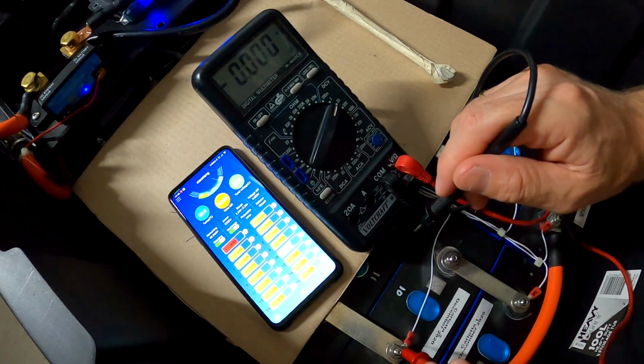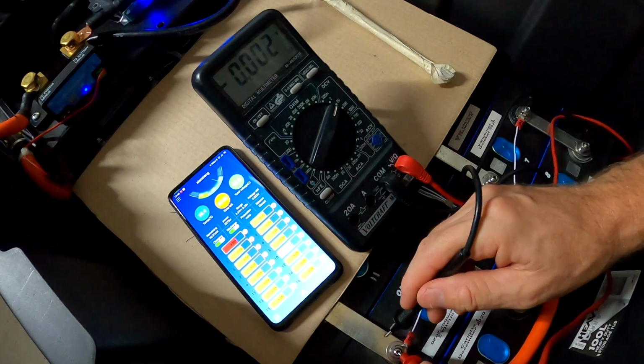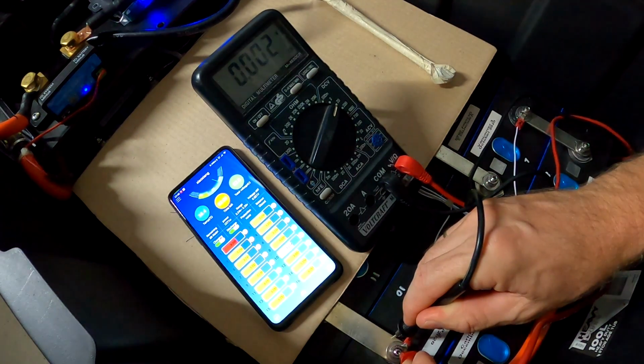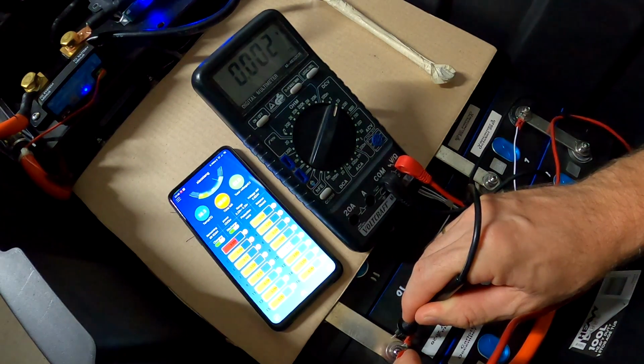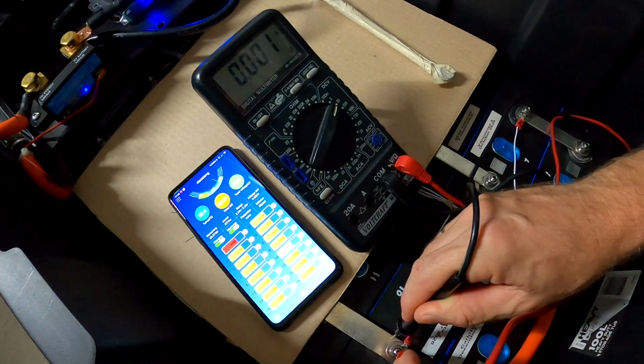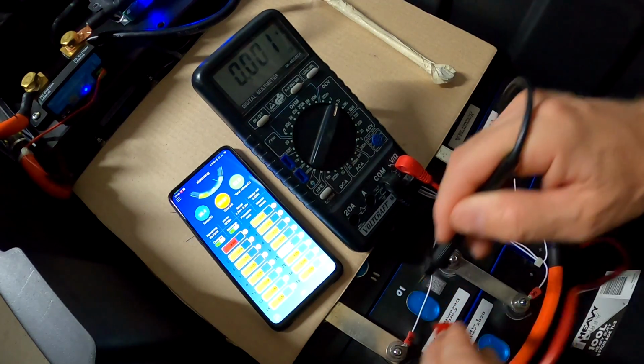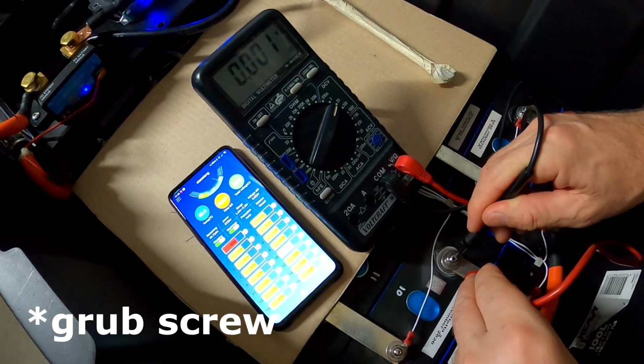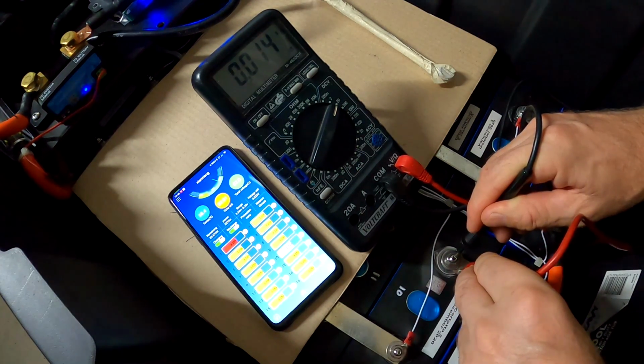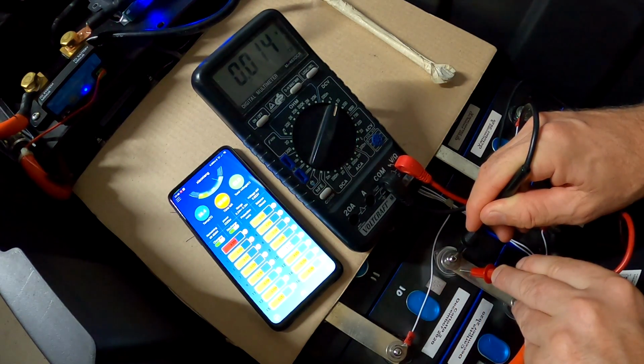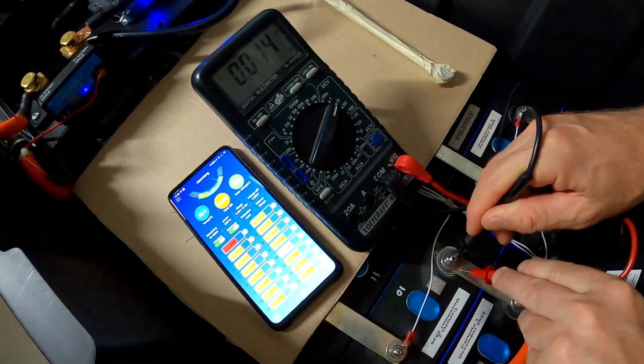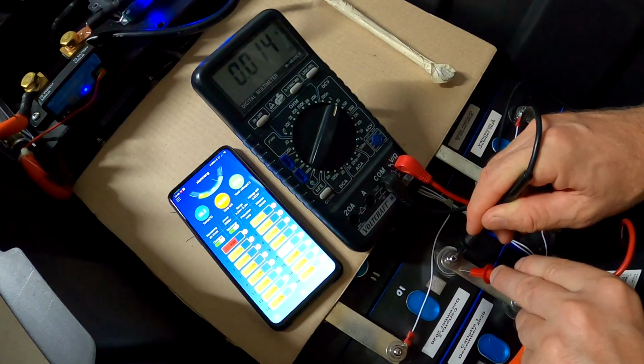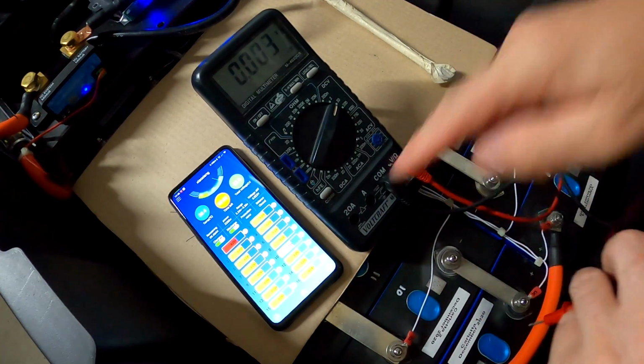Okay, so let's measure from the positive terminal here on top of the grub nut to the bus bar. We can see we've got 2 millivolt difference. The grub nut is directly connected, threaded into the terminal of the cell, so this should be the best contact we ever have, right? So 2 millivolt on this side, and we do the same on the other side, negative into the grub nut and positive on the bus bar just next to it, and we can see we've got 14 millivolt. This is from the terminal to the bus bar, 14 millivolt. And that's why the cell is so low in the BMS.